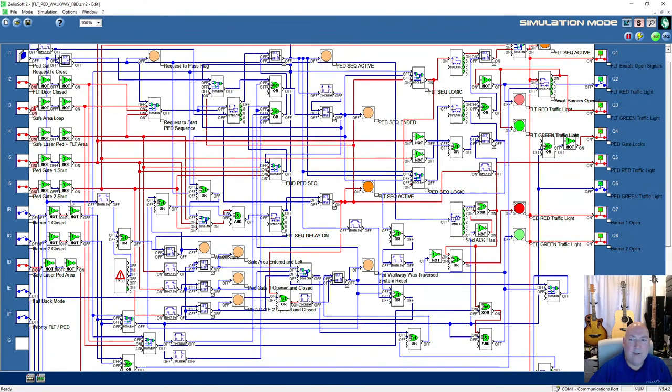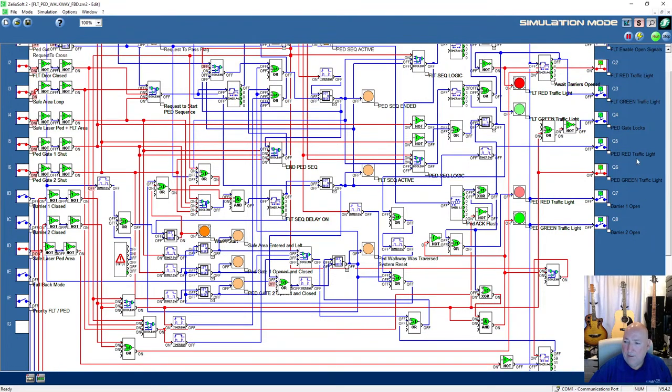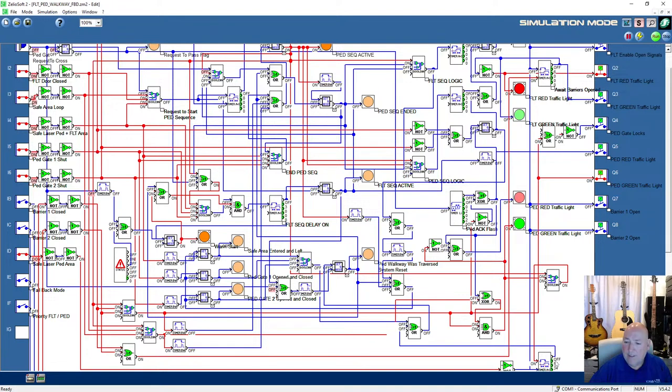Okay, we'll request a sequence. Requesting a sequence, it's changing. And yeah, it's gone to close almost straight away. It wouldn't do that in normal reality. As soon as they drop off, it needs a timer to delay. So it needs a delay on and a delay off timer, doesn't it? Really. But it's in FLT and it's counting down the sequence. Yeah, it's counting it down.